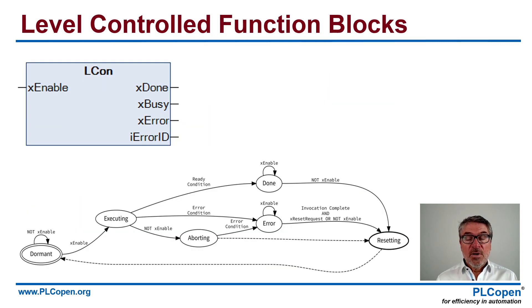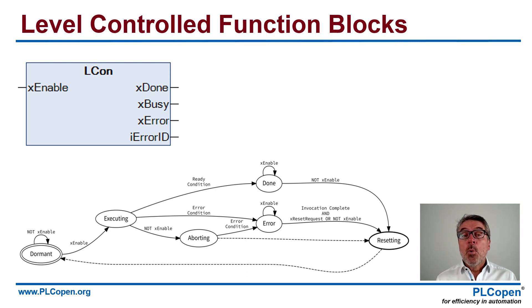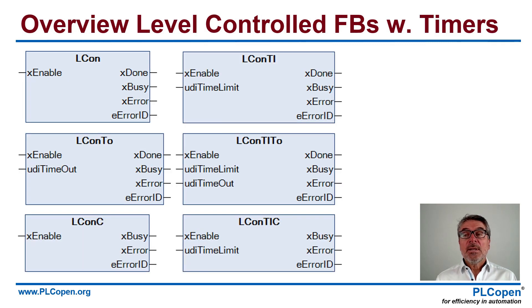The other function block type is level-controlled. Level-controlled is like your light switch in a room: if you switch it on it goes on, and if you switch it off it goes off. A usage example is the power of an electric drive — you switch it on and it stays on until you switch it off, or there is an error. You can see that in the state machine there is a state of disabling it. There we can also add the timers. Aborting is done simply by switching it off. You also see two versions with 'C' at the end for continuous, meaning it has no done output and goes on indefinitely.